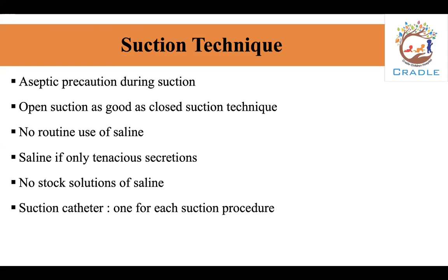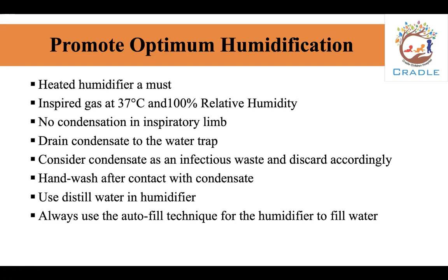Drain the condensate, and a water trap should be used to drain it. Consider condensate as infectious waste and discard accordingly. Hand wash after contact with condensate. Use a distilled water humidifier. Always use the autofill technique to fill water, because this prevents repeated opening of the humidifier, and no source of infection will enter it.